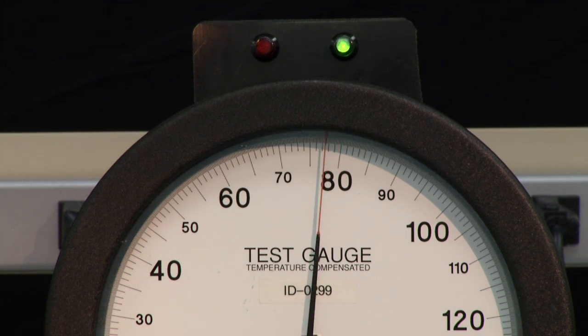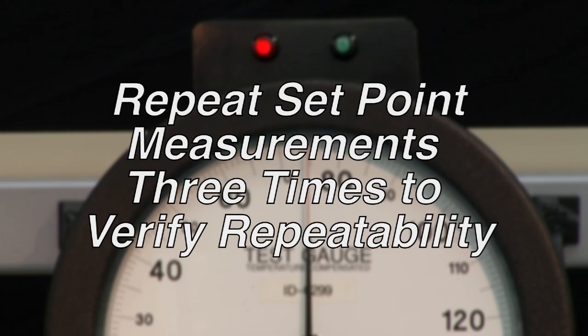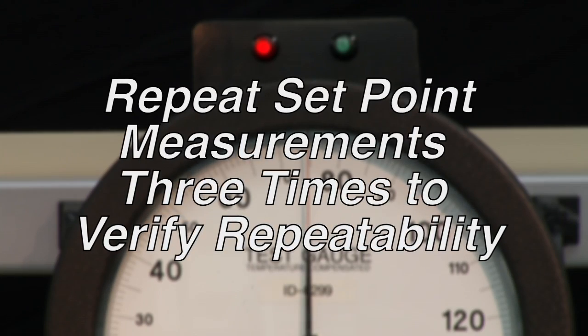We will take it back and measure the dead band. It is approximately 5 PSI. So we reset at 75. Now we would measure the switch three times for consistency.